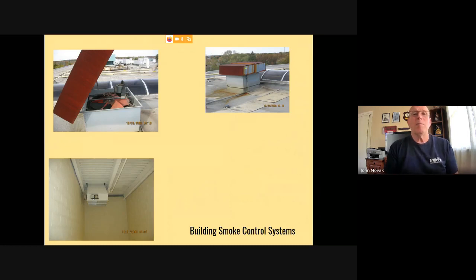So going with some of these fire protection systems, passive fire protection systems in fire-resistant buildings. There are buildings that have smoke control systems. Once you get into newer buildings where the atrium or the floor level is more than 3 stories, the atrium is required to have some type of smoke control system. So what we have here is an atrium fan, which sits on top of the roof. This is what it looks like. This is an older building, but it does have the atrium smoke control.